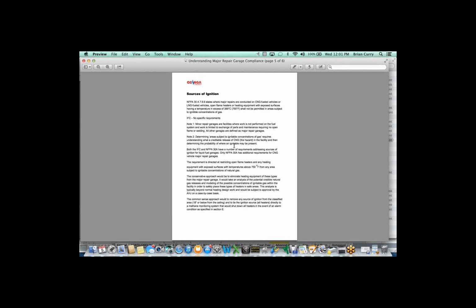Look at where you're putting the methane system. Look where the gas is going to rise, and determine whether or not, practically speaking, that heater's in an area where there could be a combustible buildup of gas, more combustible than where the gas is going to find the methane detector. And if you see that it's close, the best call, use your judgment: move the heater.